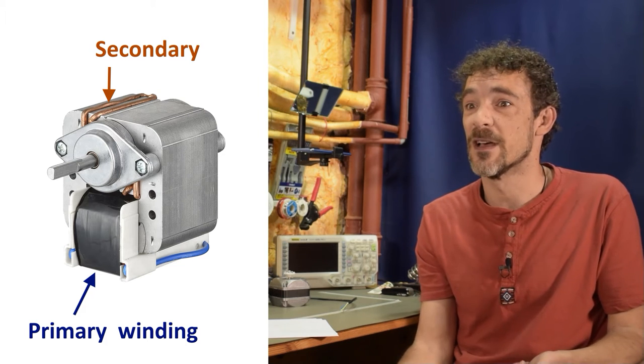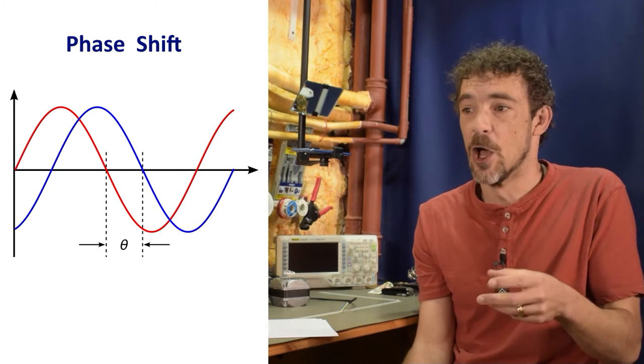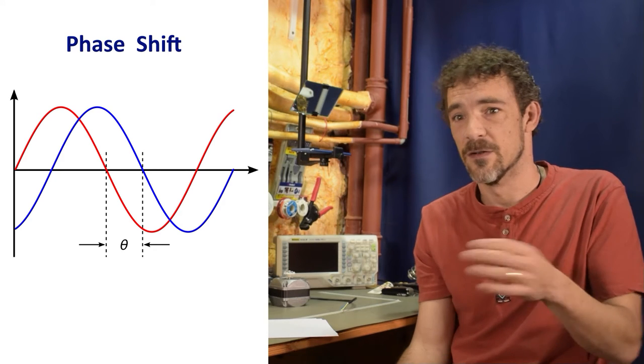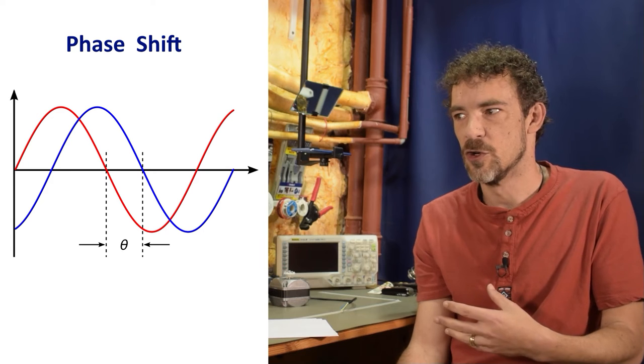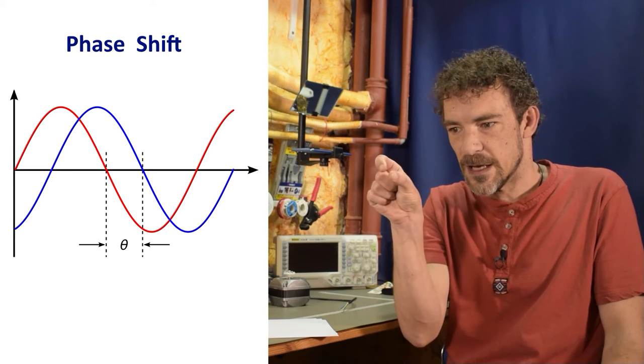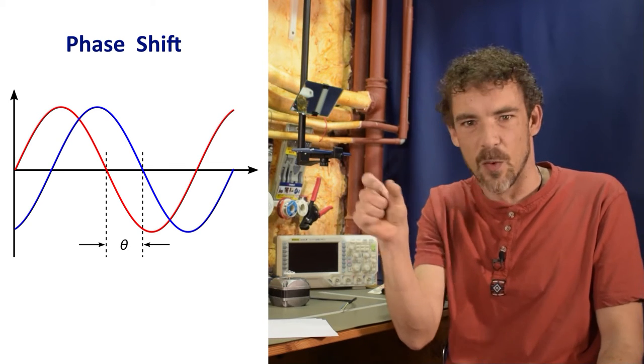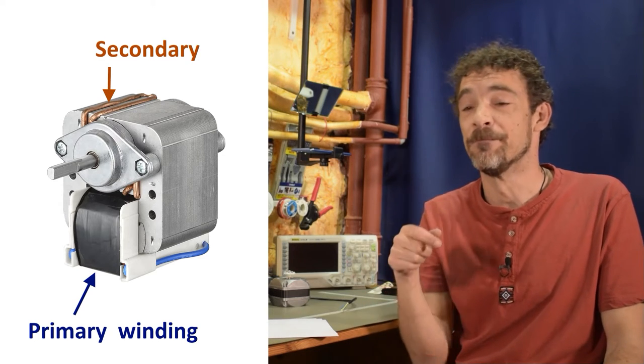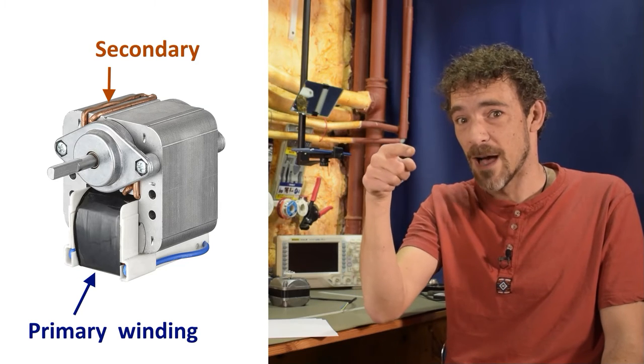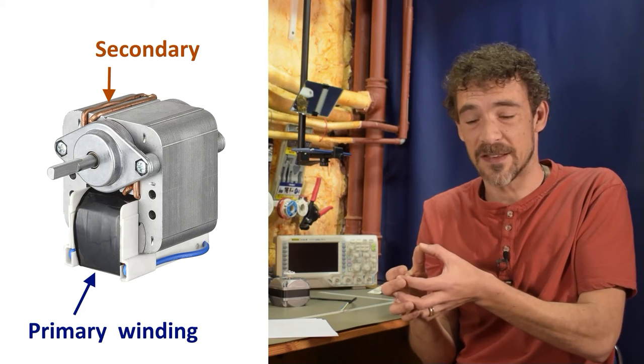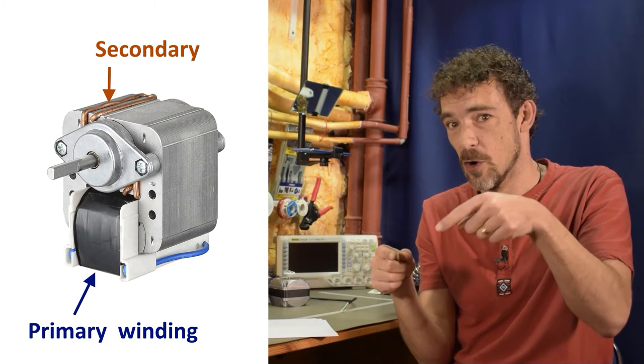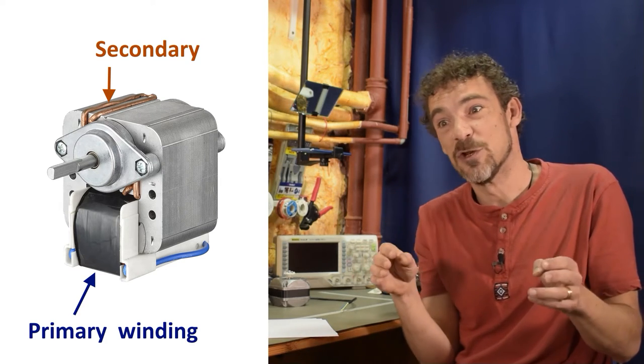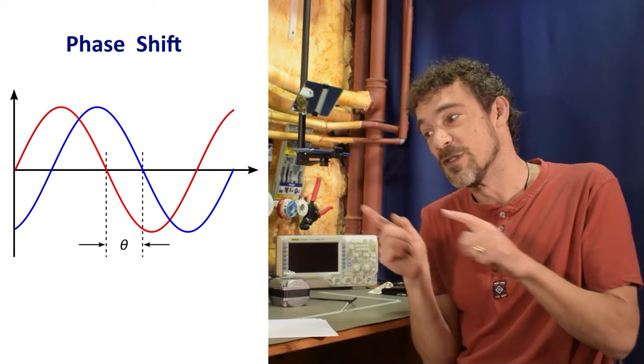And then you'll notice this little secondary winding. That's actually the shading coil. Now, as you probably know, when you have a single phase alternating current, right, one phase, when you put that into a motor, as we know, the current goes, it kind of goes like this and it's a sine wave. So the current switches directions X number of times a second. So normally if you applied that alternating current to one of these motors, what you'd end up with is basically it would kind of turn this way a little bit, then the current would switch directions and it would turn back, turn this way, turn back. It'd kind of wobble in place more or less. So what they do is they add this shading coil and all it is, there's several different ways of doing it. But in this example, it's simply a fat turn or two of copper wire installed in such a way that when the primary coil is energized by your single phase AC that creates an electromagnetic field, it also induces a current in that shading coil. And as we know, when you induce a current in something, it creates its own electromagnetic field. That electromagnetic field, that secondary field just happens to be out of phase with the single phase AC that you're using to power it. And that's what actually, instead of making it wobble, it actually makes it start turning.